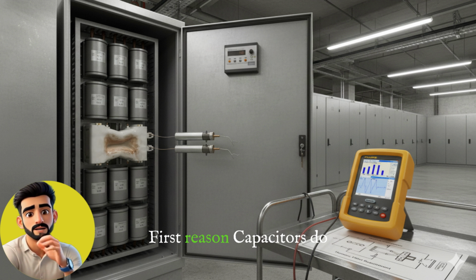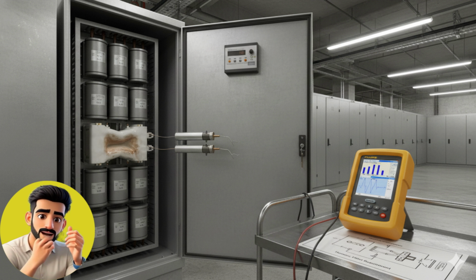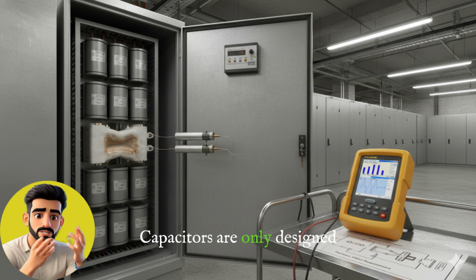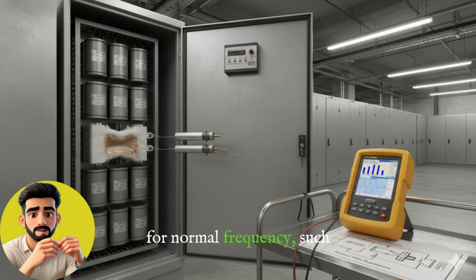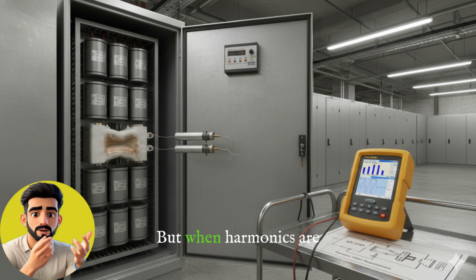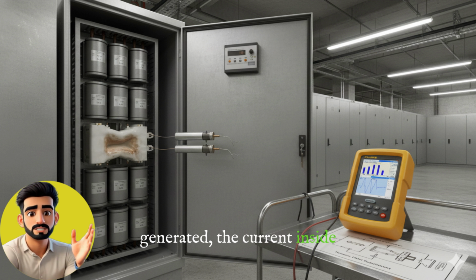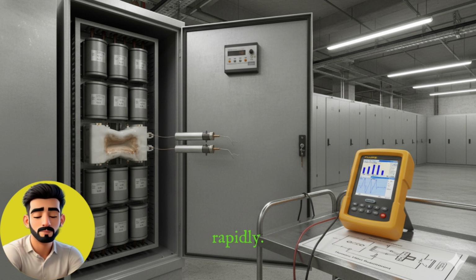First reason, capacitors do not like high frequency at all. Capacitors are only designed for normal frequency, such as 50 Hz. But when harmonics are generated, the current inside the capacitor increases very rapidly.